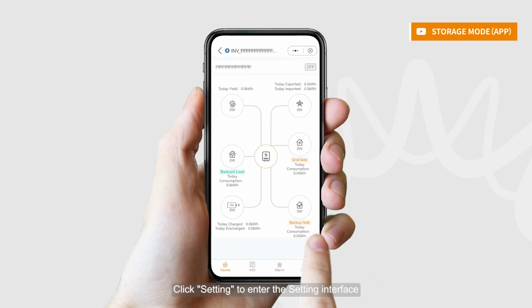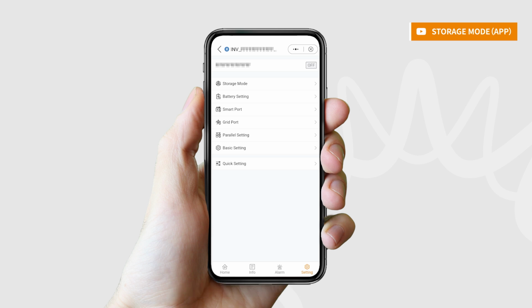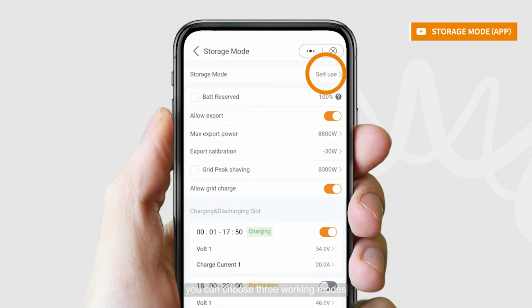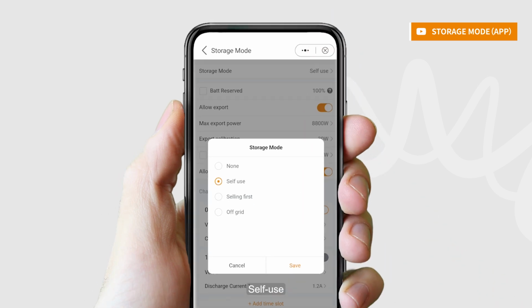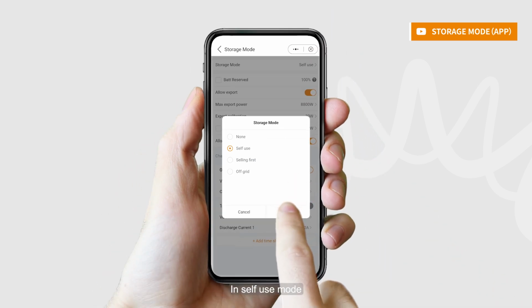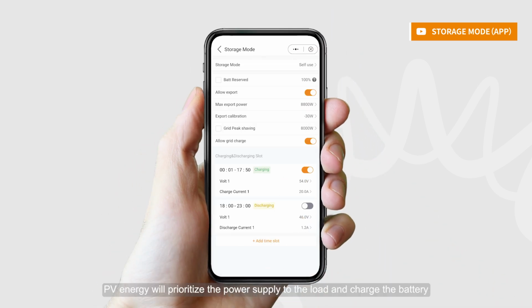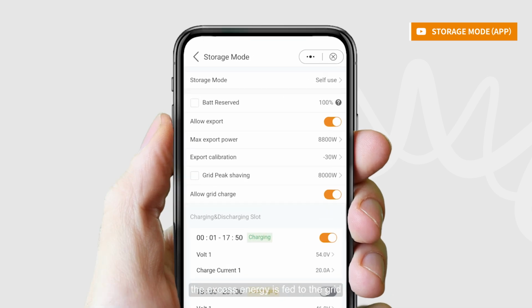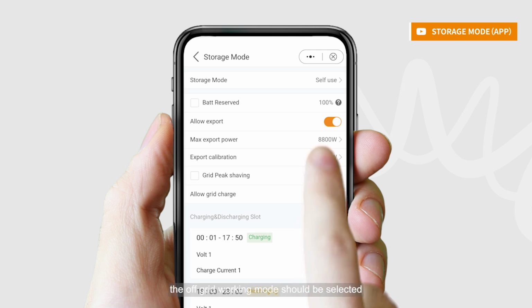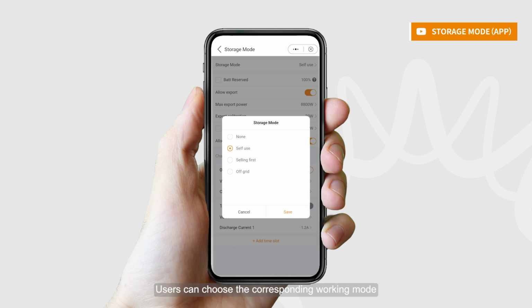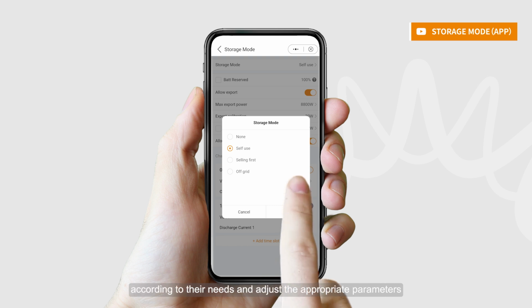Click Setting to enter the setting interface. Click on Storage mode. On this interface, you can choose 3 working modes: self-use, selling first, and off-grid. In self-use mode, PV energy will prioritize the power supply to the load and charge the battery. The excess energy is fed to the grid. When there is no power grid, the off-grid working mode should be selected. Users can choose the corresponding working mode according to their needs and adjust the appropriate parameters.